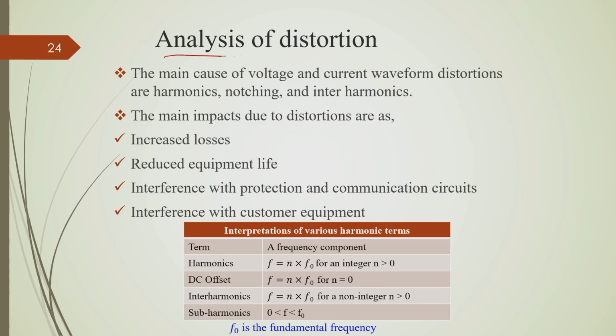Now, we also go for different other analysis of distortions. As I said, here we are basically trying to understand how do we characterize this distortion. Okay. So, there are some periodic distortion and there are some non-periodic distortion. These periodic distortions are basically harmonics, in fact, notching as well, and also interharmonics. Okay. And the impact of these distortions, they will create increased loss, because I will show you that any distorted periodic waveform can be resolved into a number of sinusoids with different frequency, out of which fundamental frequency component is important for us, because that is what we are trying to provide to the customer as an electric utility.